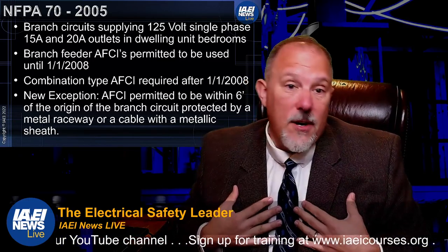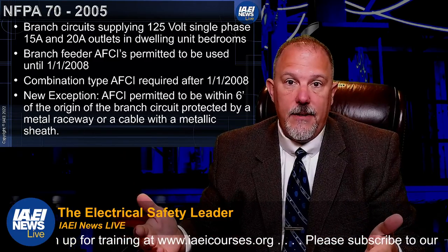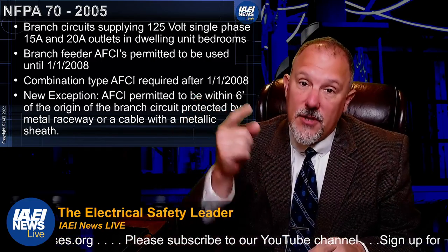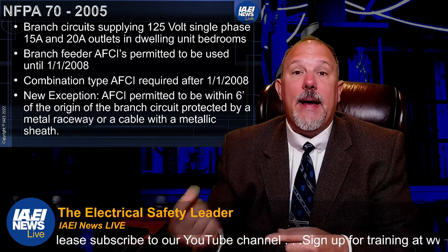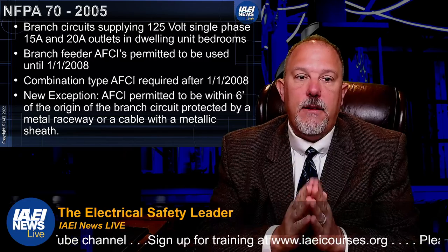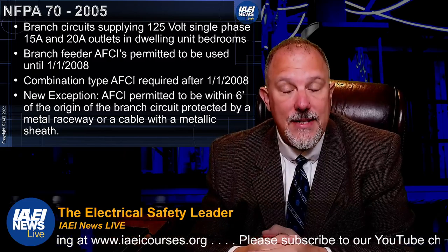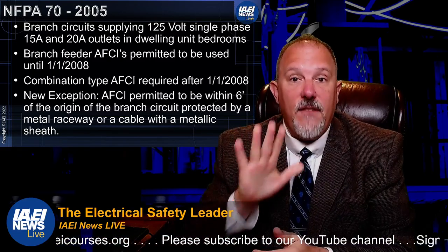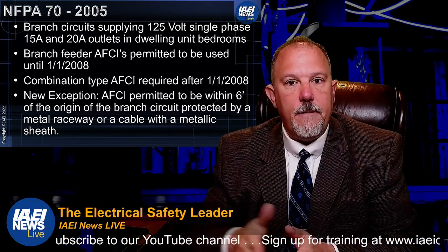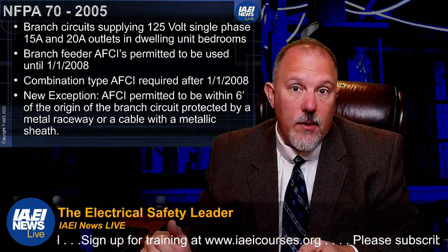Personally, I dislike the word 'combination.' A lot of people mistakenly think combination AFCI means AFCI plus GFCI — that is not correct. A combination type AFCI, as explained last week, has one test in the UL 1699 standard to detect a 5-amp series arc in SPT-2 cord. That's the only additional thing the combination type brings: 5-amp arc fault protection of a connected cord without an equipment grounding conductor.